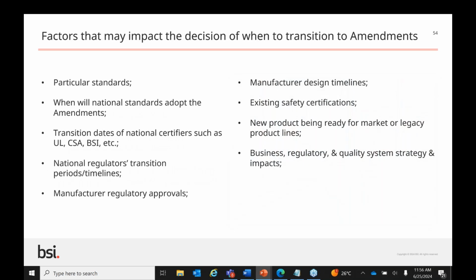So what are the factors that may impact the decision of when to transition to the amendments? The particular standards which I talked about early in the presentation. When will the national standards adopt the amendments? So for the US, AAMI, the national standards organization, has adopted the US versions of IEC 60601-1, 1-2, 1-8, 1-11, and 1-12 around spring of 2021. They won't adopt any of the other standards because those are the ones they deal with. For Europe, CENELEC has published all the EN general and collateral standards based on the amendments project, and then each European country has to adopt the EN standard, and that should have been done by now based on the date of publication requirement, I think it is.